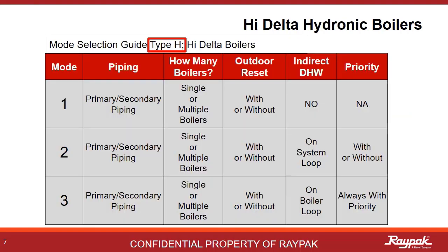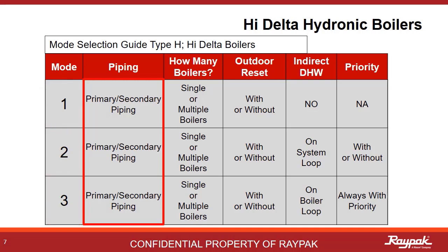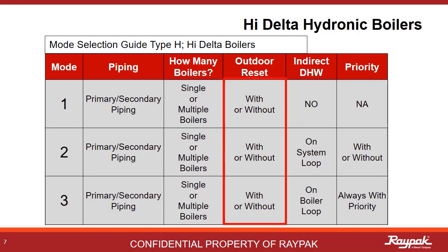This is a summary table for the hydronic-type boilers. There are three modes to choose from: Mode 1, 2, and 3. All must be plumbed primary-secondary, as the high-delta boilers are low-mass. All three modes can be applied to single or multiple boilers, and all can run with or without outdoor reset.